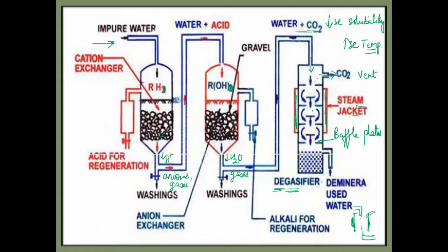So basically, because of this baffle plate, the surface area is increased, right? So better, uniform heating will take place. Because of that surface area, uniform heating will take place because these plates are also getting heated. Secondly, it will increase the retention time. Retention time of the molecule. The water is coming down, but if it is not spending time here, it may come out from the container very easily, and in that duration it might not get heated.